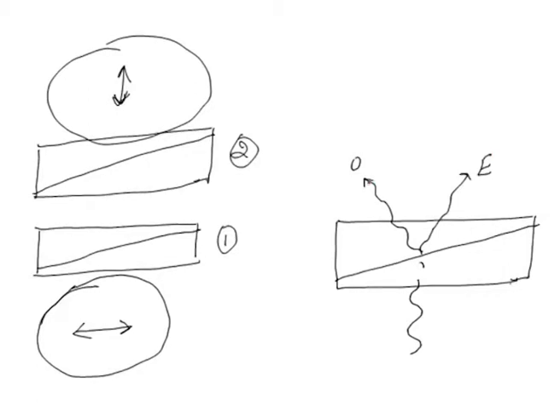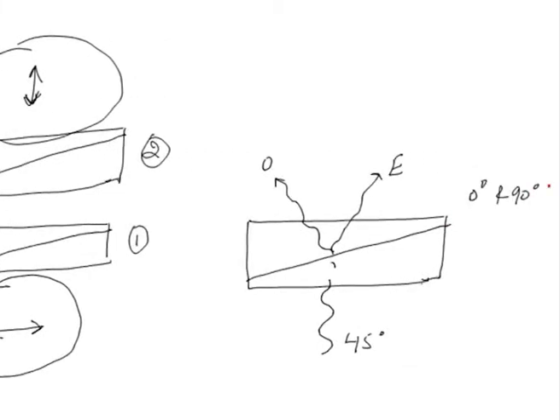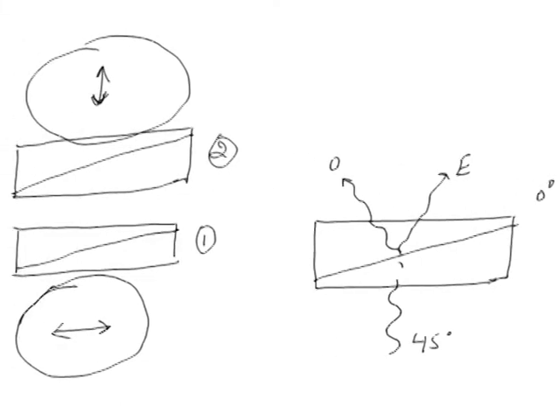These two rays are spatially separated — or 'sheared' — meaning they are moving adjacently in the optical path. These two sheared rays are perpendicularly oriented to each other, at 0 and 90 degrees. The light enters the prism, passes through the condenser lens, and the adjacent rays are focused onto the specimen plane.